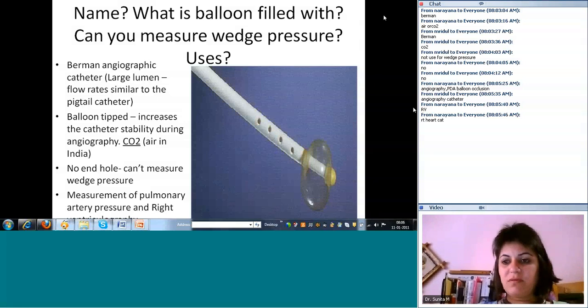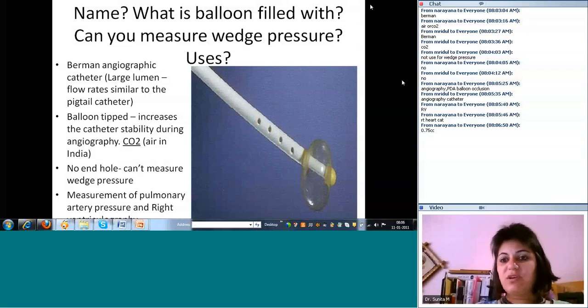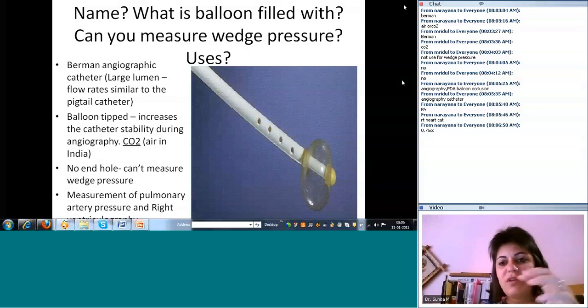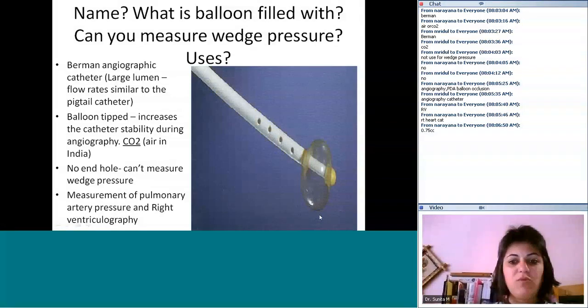Around half centimeter, 1 centimeter, okay, 0.75 or 1 cc. So you're not going to get it very large, maximum a centimeter, and typically less than that. So a 6-7 mm duct you could, but if you have like a 12 mm duct, 14 mm duct, you can't use a Berman, then you have to use another catheter. Okay, so all clear on the Berman catheter. We'll move on to the next catheter.